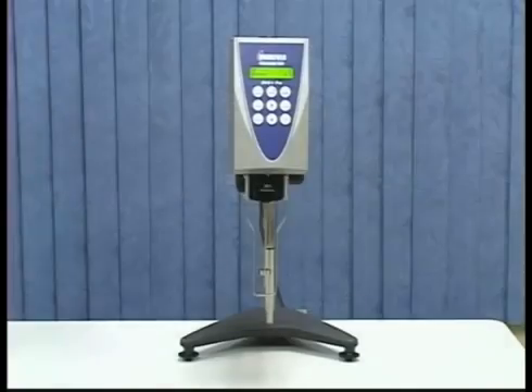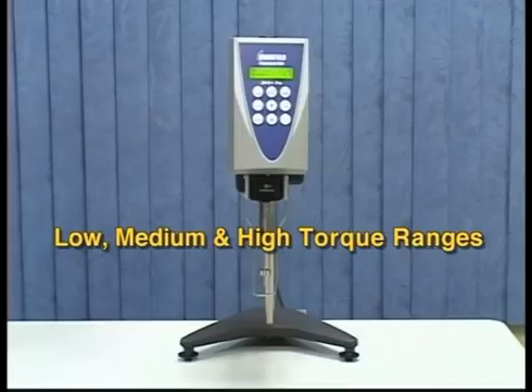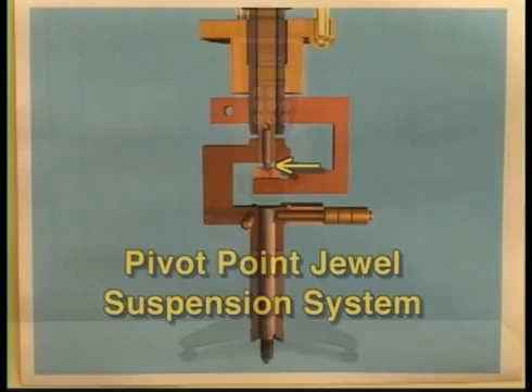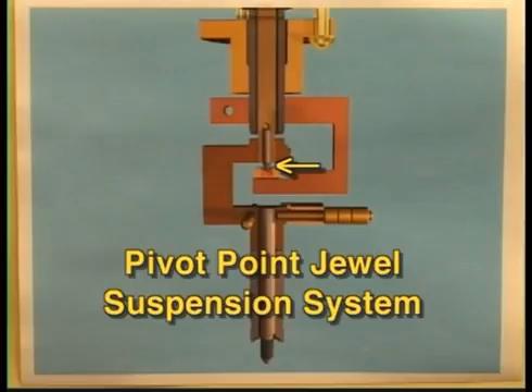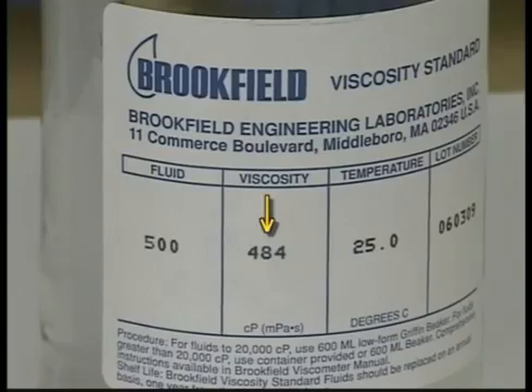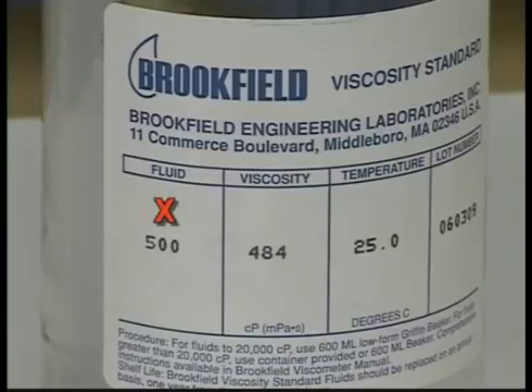The calibration routine checks the linearity of the spring on the instrument by using one fluid at 3 separate speeds to achieve low, medium, and high torque ranges. This checks the linearity of the spring and the sensing mechanism of the instrument. Use the actual value of the fluid, not the stated value, for the calibration check. Make sure the instrument is level.